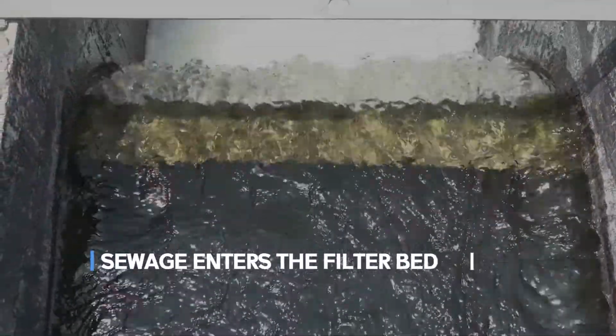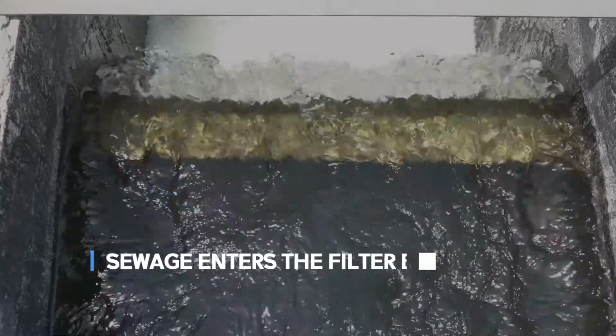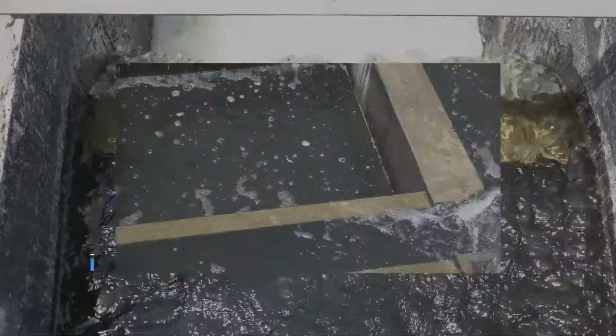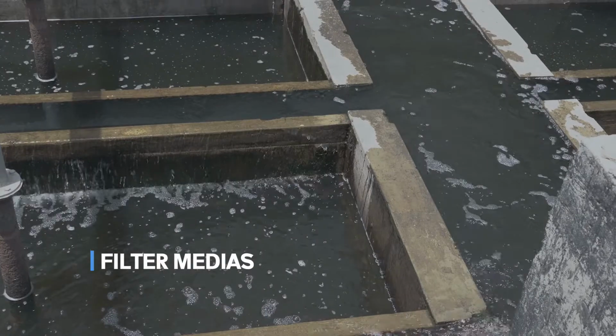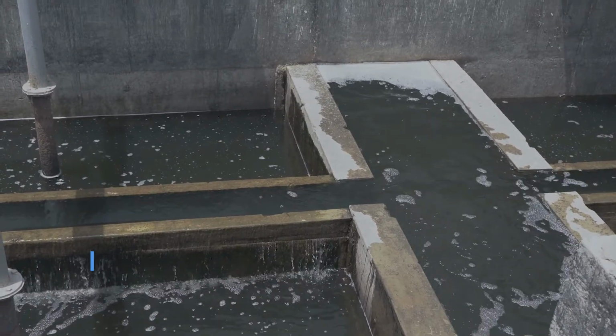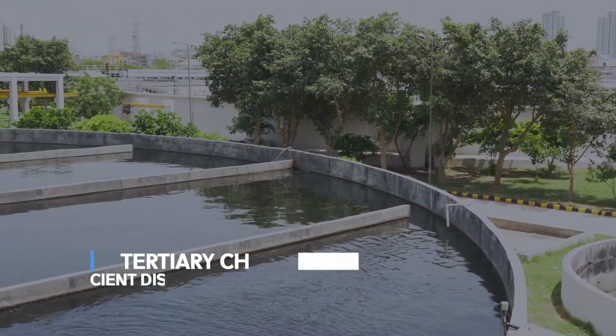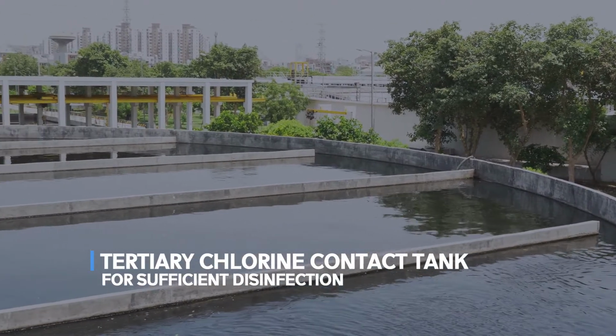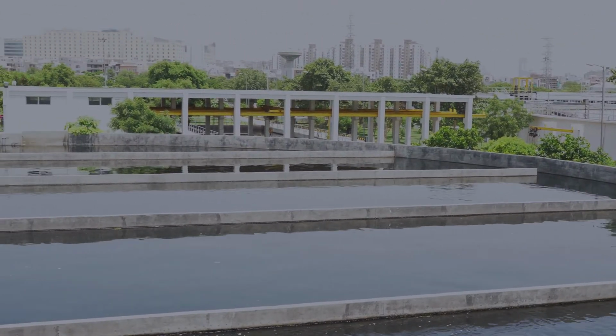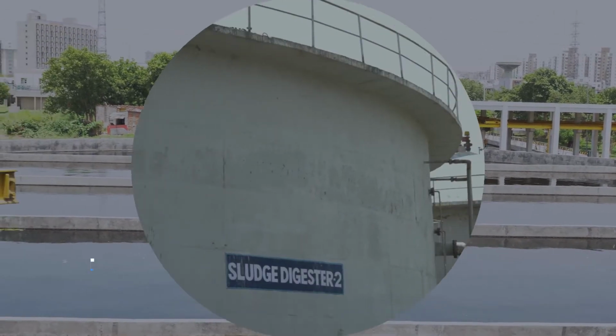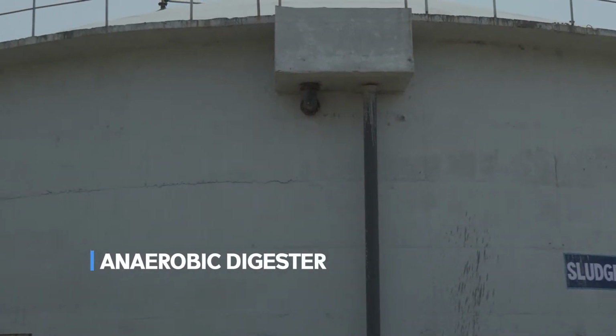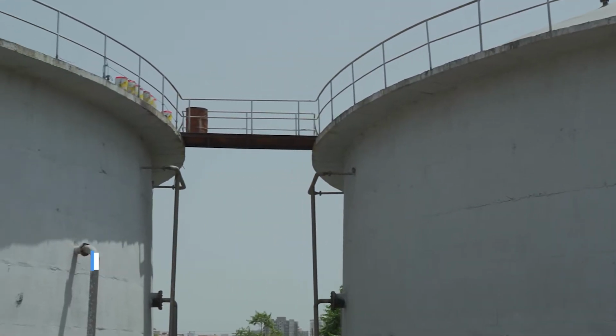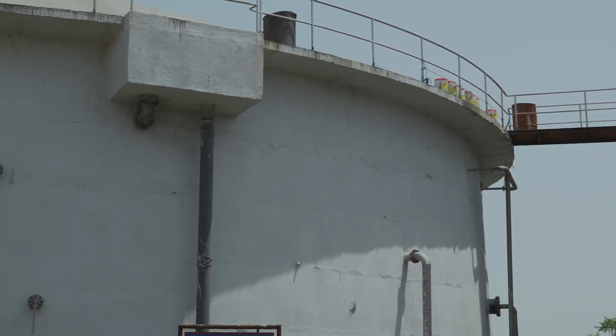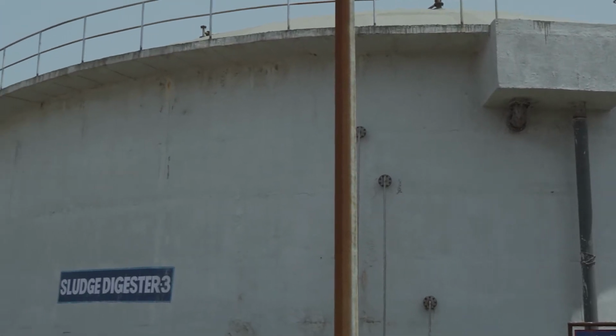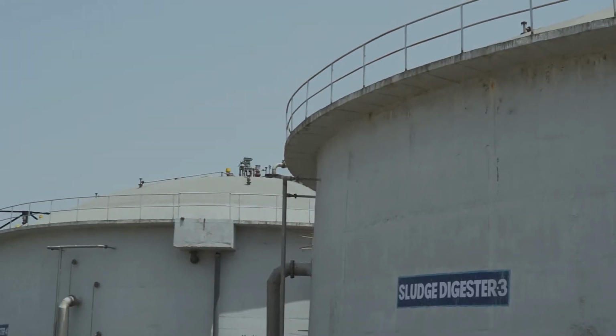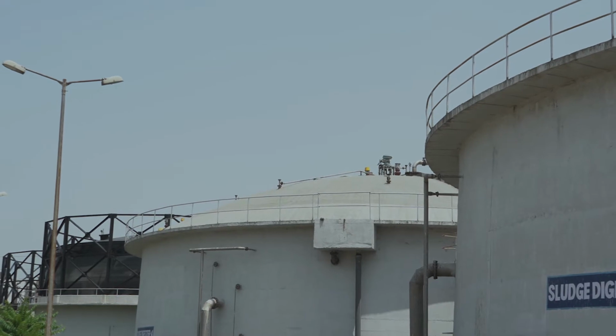After the clariflocculator unit, the sewage enters the filter bed, of constant head and constant flow type. A total of 4 filter media are provided for 30 MLD sewage filtration with maximum filtration rate. After the above filtration, further disinfection is done using chlorine gas at another CCT. Sludge generated from the primary clarifier and biological treatment unit is collected into the combined sludge sump. Thickened sludge of 5% consistency is fed to the anaerobic digester in order to reduce putrescibility.